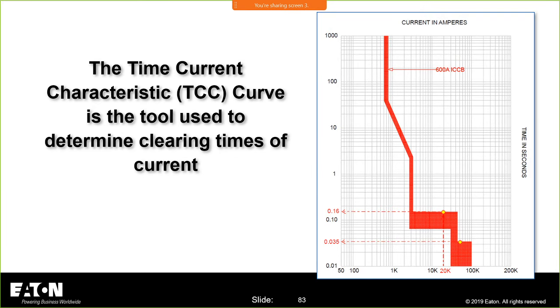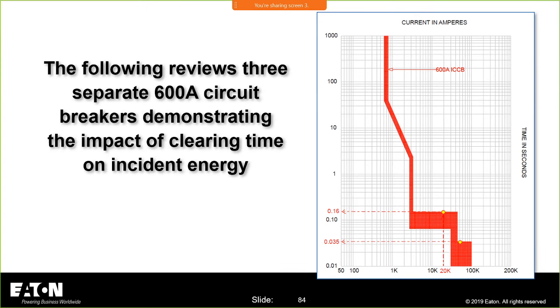Circuit breakers as well. This time current characteristic curve that we use in our coordination efforts is used to establish incident energy. And just think that if I didn't maintain my breaker, and instead of a 0.16 clearing time, it takes a lot longer to clear, I'm adding time to the clearing of my arcing current, which adds incident energy. Maintenance is very important on a power distribution system. You will see limited examples in the National Electrical Code where we talk about maintenance. That is why we have NFPA 70B, as in Bob. That talks about maintenance. And we have resources from NEMA, National Electrical Manufacturers Association, that we can download to help us understand what you can and can't do to perform maintenance on things like molded case circuit breakers. But if you don't maintain your electrical distribution system, you can't expect it to respond in the time that it needs to respond.